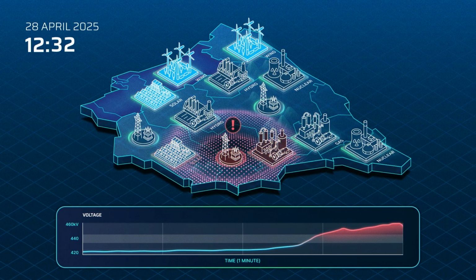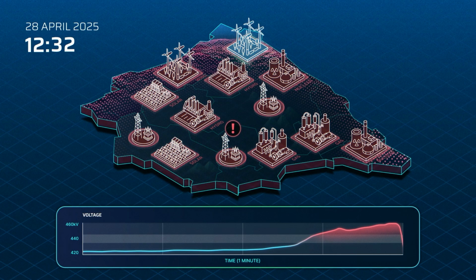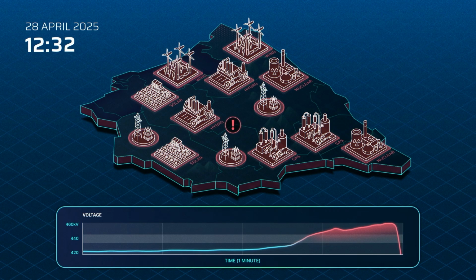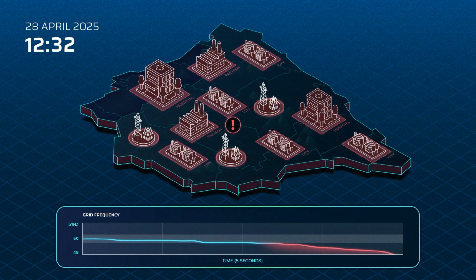At 12:32, the crisis struck. A critical substation tripped from overvoltage, triggering a blindingly fast chain reaction. Generation assets across the peninsula detected the spike and disconnected to protect themselves, causing further voltage spikes. As generation vanished, grid frequency dropped below 49 Hz, triggering automatic load shedding across the peninsula. Within seconds, Iberia collapsed into a total blackout.